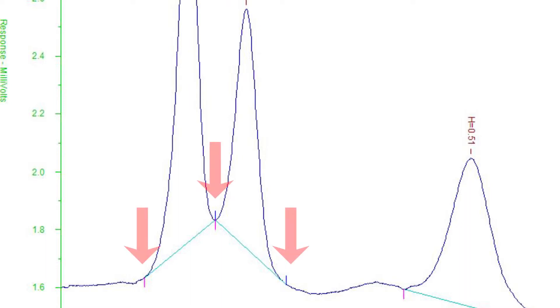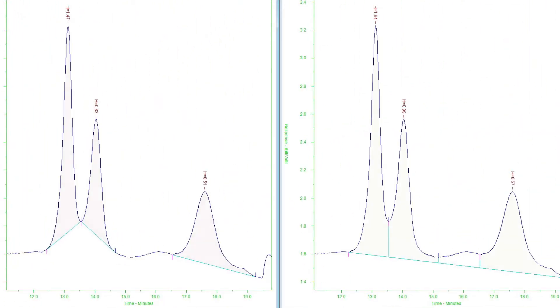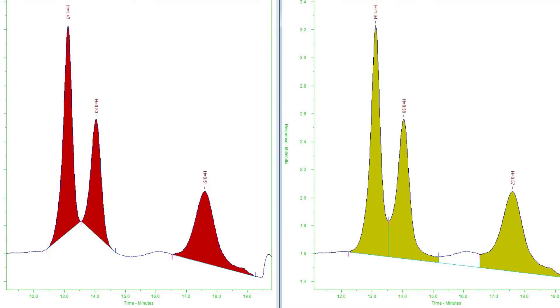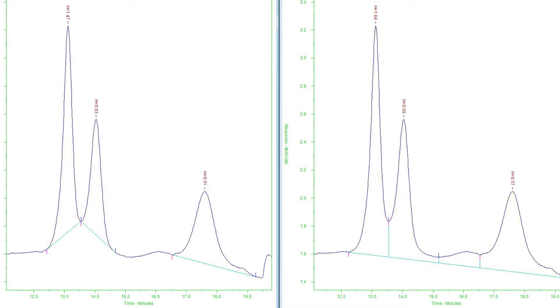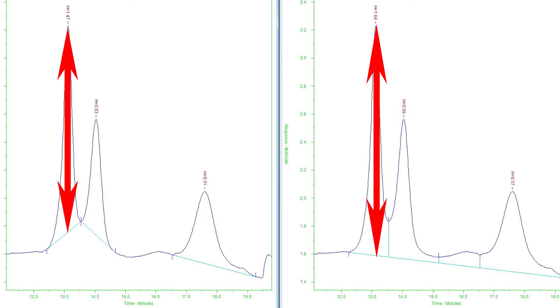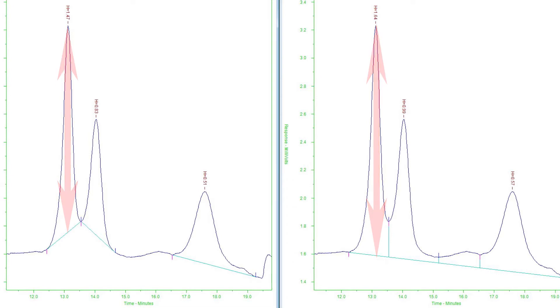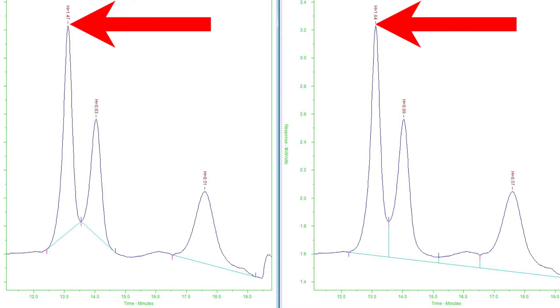These points are marked by the small vertical tick marks projecting downward at the peak start and upward at the peak end. The peak area is defined as the area between the chromatogram and the baseline. The peak height is defined as the greatest distance measured vertically between the chromatogram and the baseline. The point corresponding to this greatest distance is the peak top, and the time of this point is the retention time of the peak.